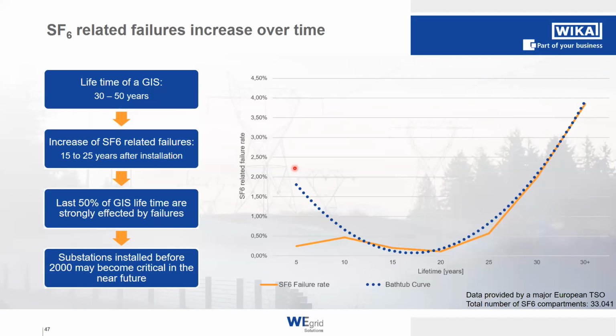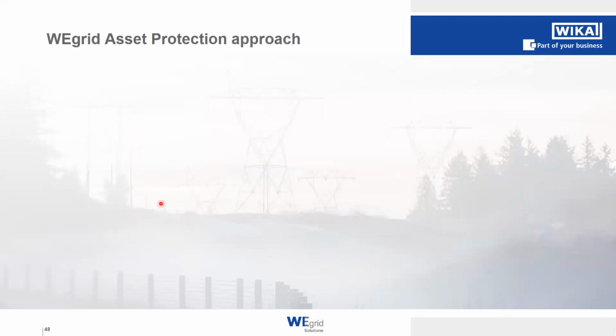A significant increase of failures after 20 to 25 years, mainly due to the wear out of equipment caused by the facts that we have seen before. And especially in Europe, these old GIS make out more than 56% of the installed base. And if a GIS fails unplanned, it can lead to power outages and huge costs to the operators. And this is what we want to avoid with our system.